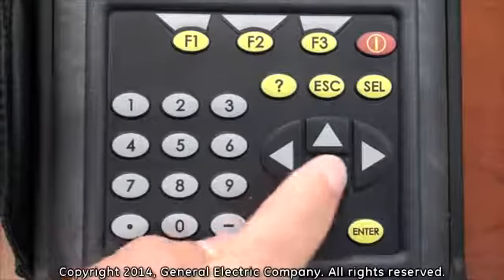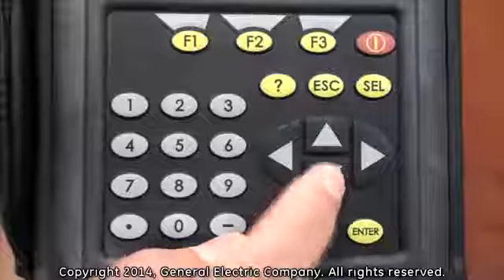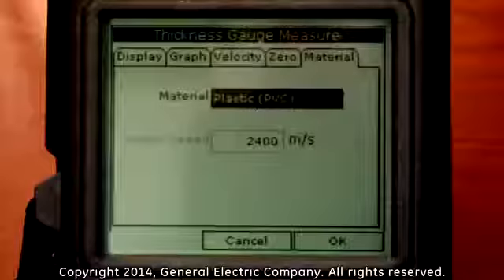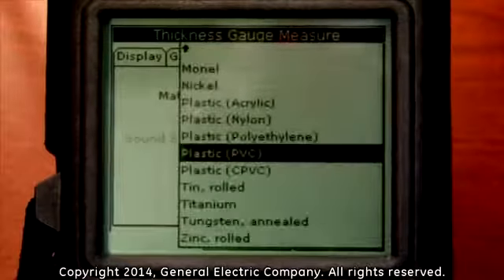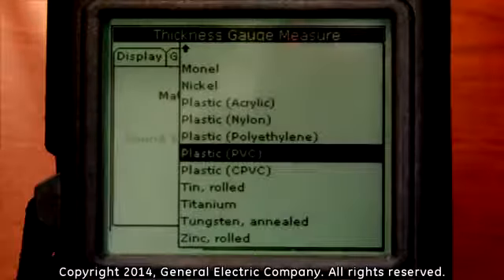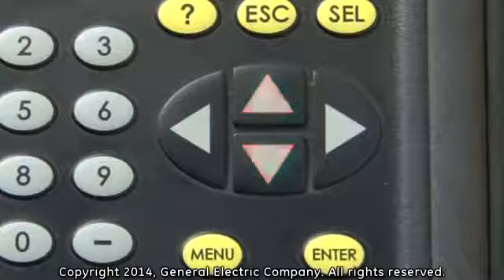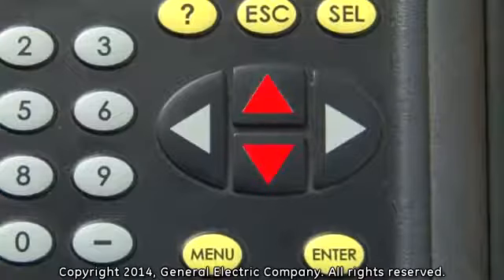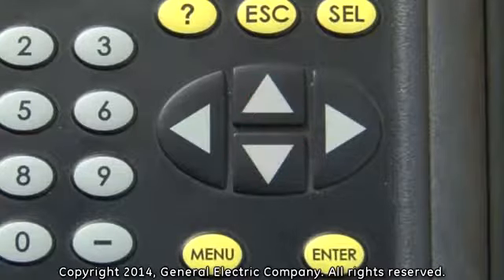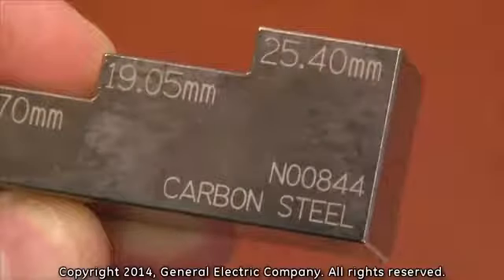Press the down arrow key on the keypad to highlight the material field and then press the Enter button on the keypad. A new drop-down menu appears with multiple material options. Use the up and down arrow keys on the keypad to highlight the material type you are using to calibrate your thickness gauge. The material type should be printed on your calibration test block. For this example, we are using a carbon steel test block.